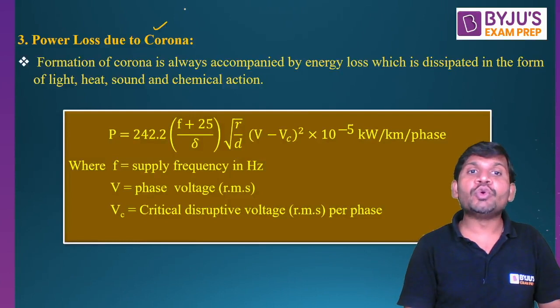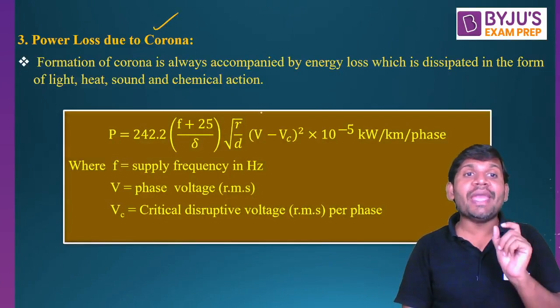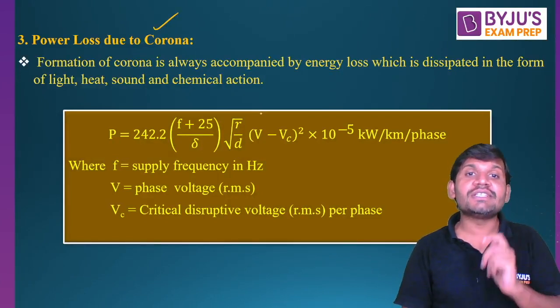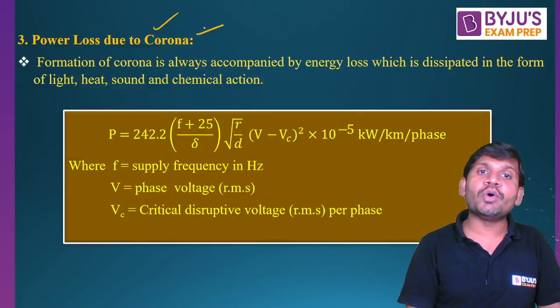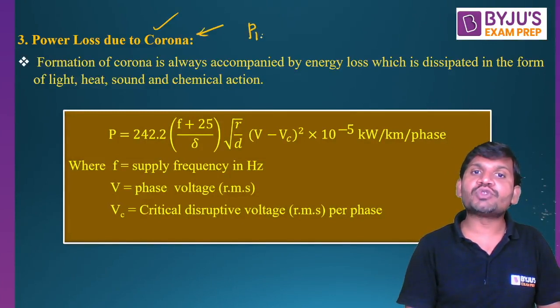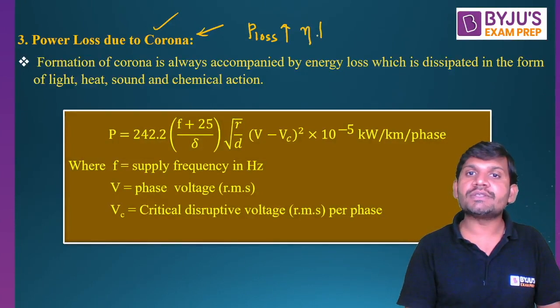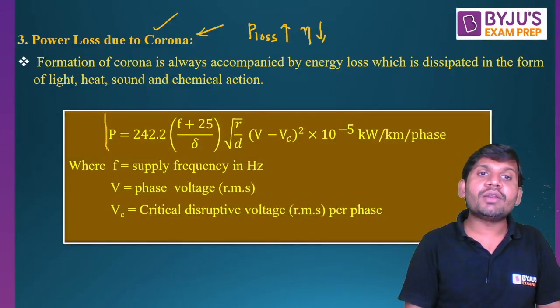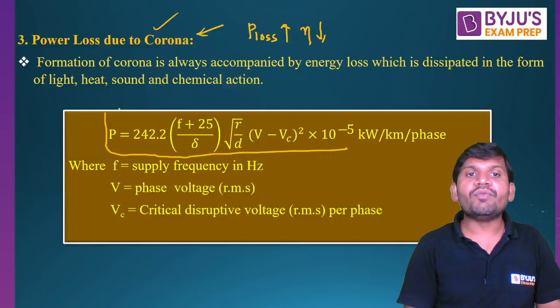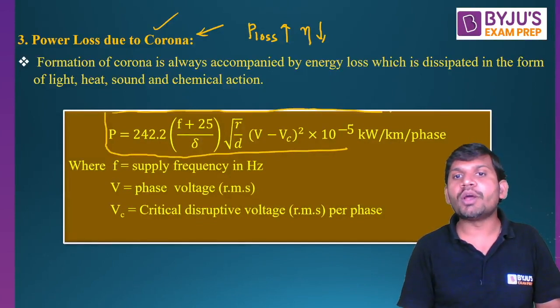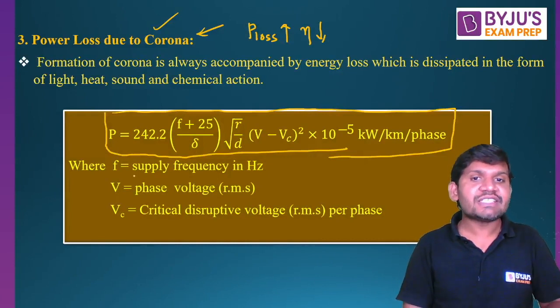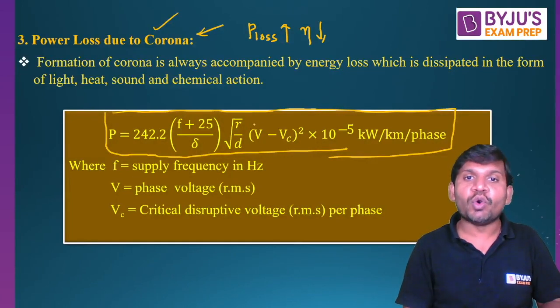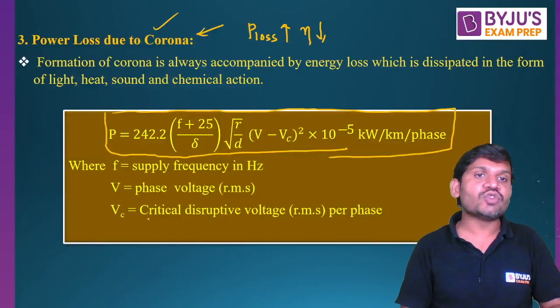Then, power loss due to corona. The main effect of corona is that it causes power loss. Due to the corona effect, power losses increase and efficiency is reduced. This is the formula for the power loss expression — a very important formula to solve problems. In this formula, F is the supply frequency, V is the phase voltage (the system voltage), and Vc is the critical disruptive voltage, which is also a phase voltage.